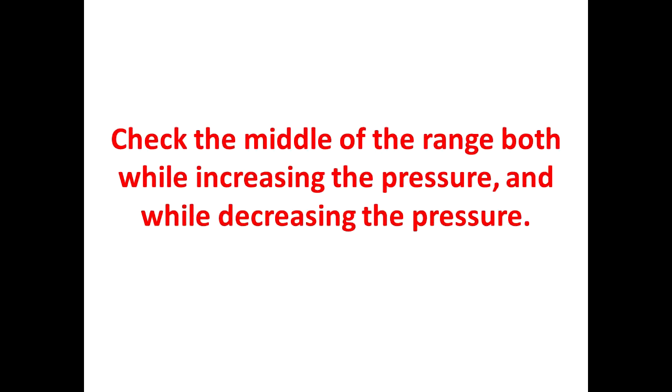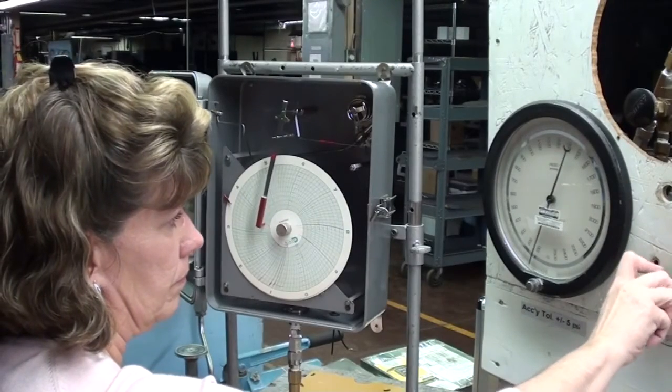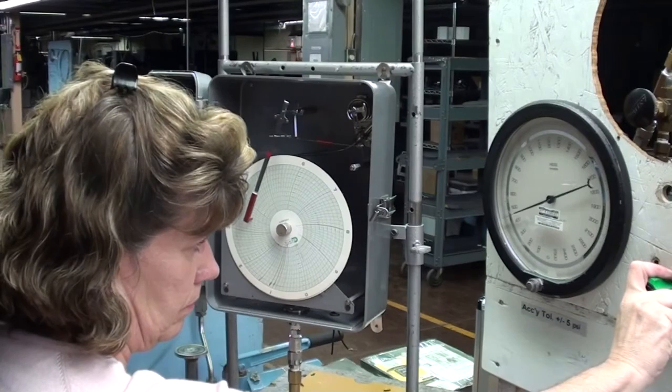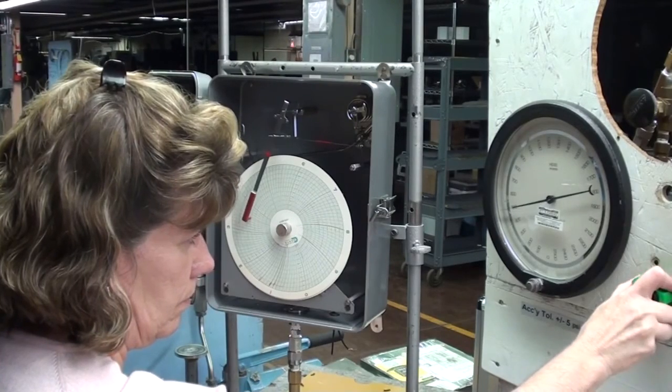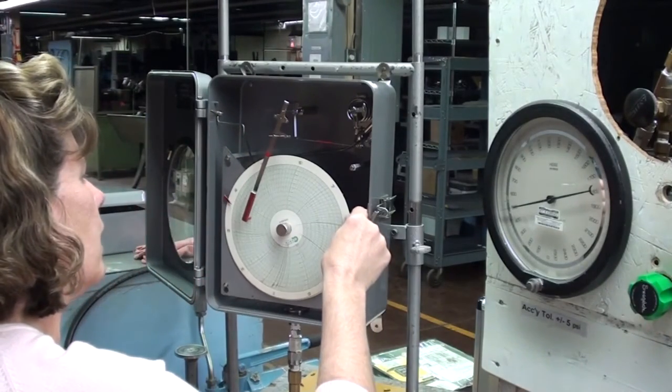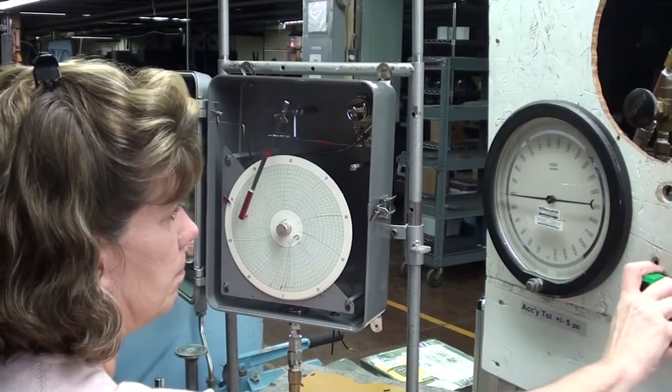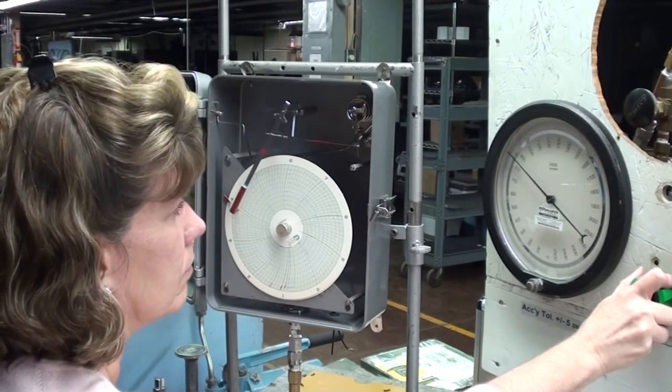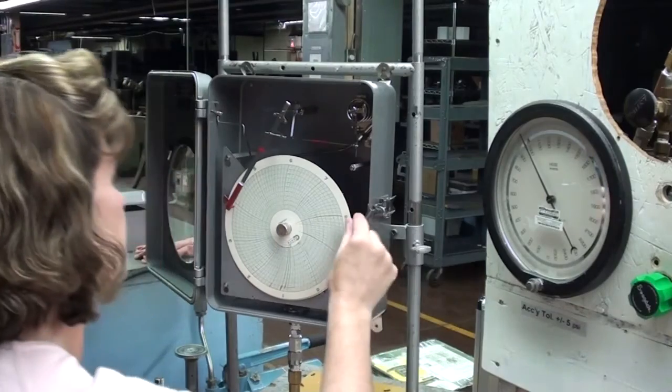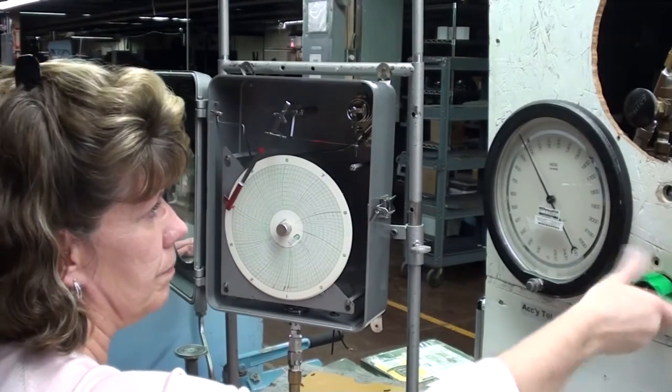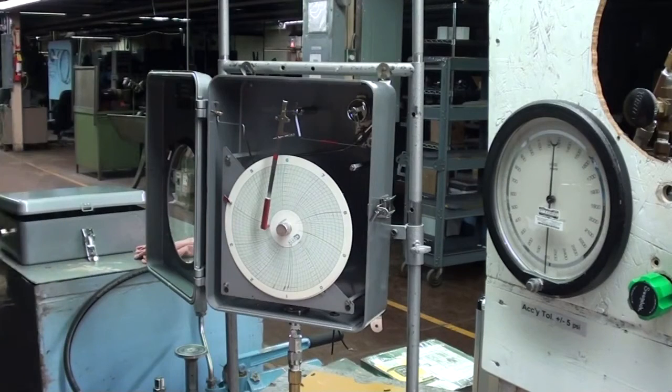So, I was at the bottom, top, and I did the middle coming down. So, now I'm going to do the middle going up. Okay. There's 500 psi going up. Let's just go on to 1,000, double check our top. Okay. That's the calibration of our recorder.